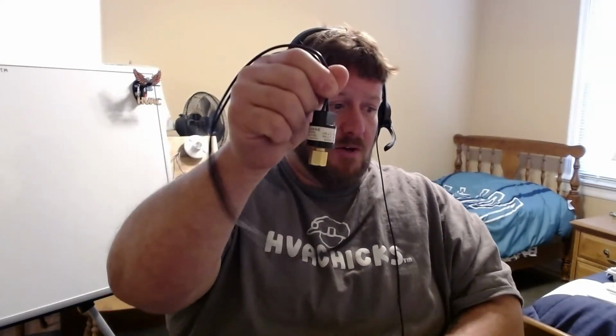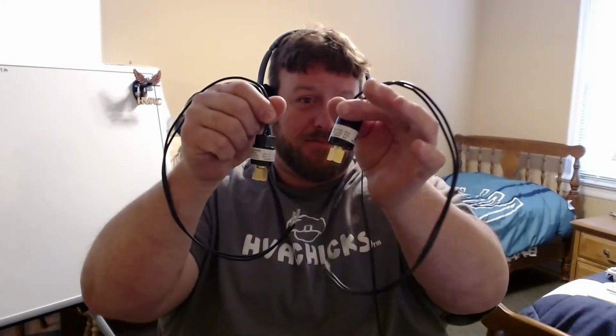Now, like I said, I'm covering so I can't see which one's which. So this is my low pressure. This is my high pressure. You can't tell because the numbers are hidden. But if you can't read the numbers on here, if something happens and you know you have a 410A high pressure, low pressure switches, you're not sure which one it was, that is one way you can figure it out.